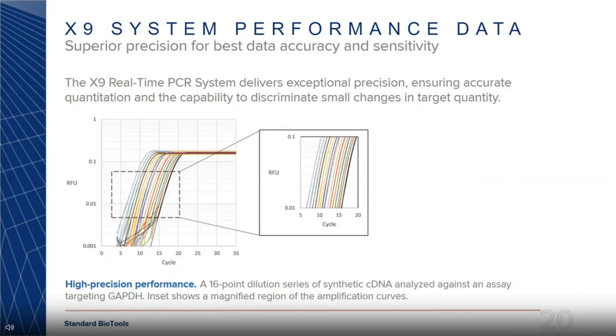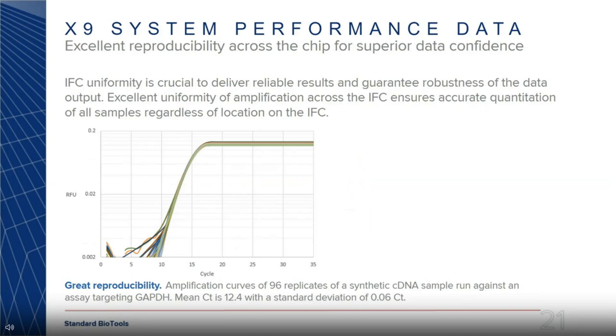Here's data showing the precision of the system. We took a GAPDH assay, ran a 16-point dilution series, and the qPCR curves show replicates all on top of each other — high precision for gene expression assays. For reproducibility, we took 96 replicates of a cDNA sample run across the chip, and at a mean CT of 12.4, the standard deviation was 0.06 — pretty tight compared to industry standard.